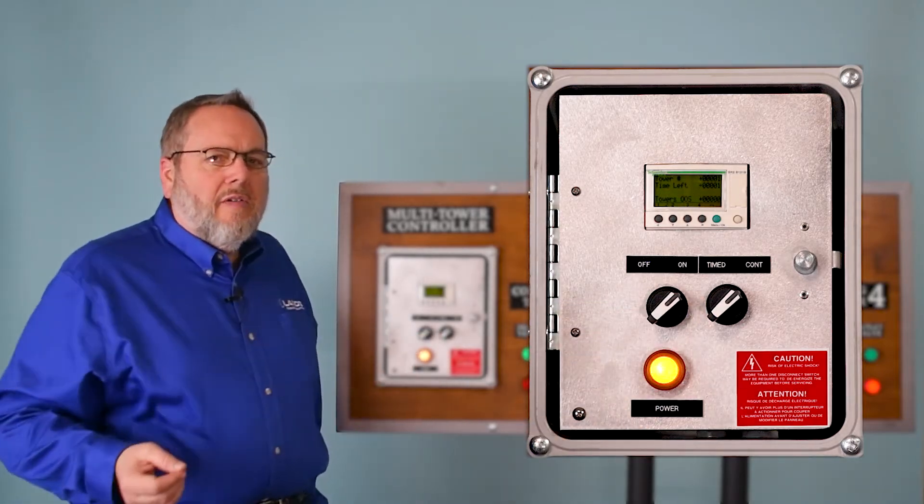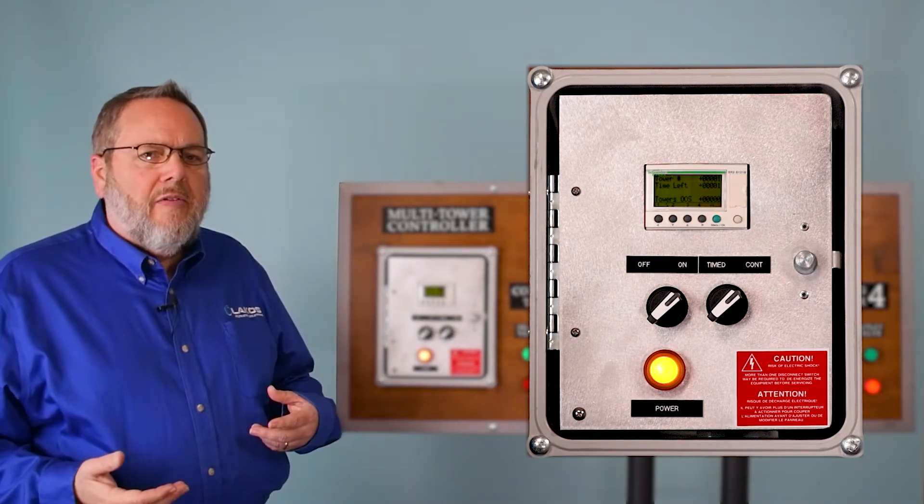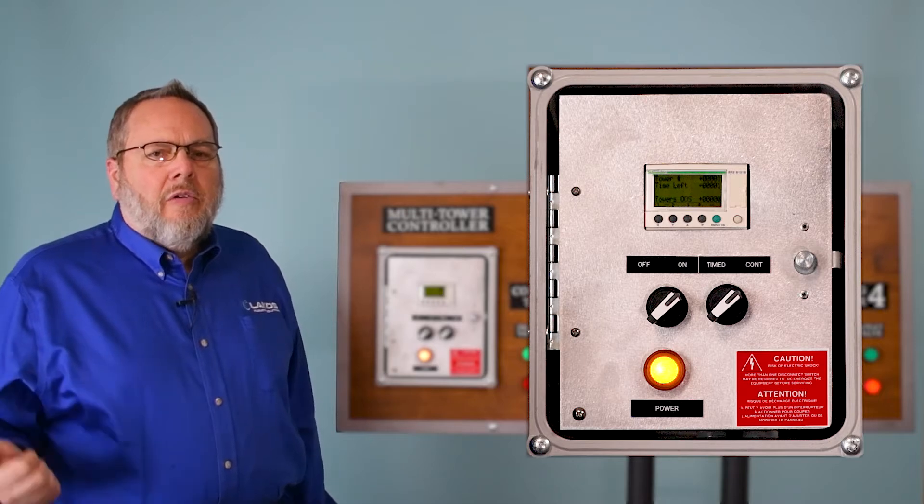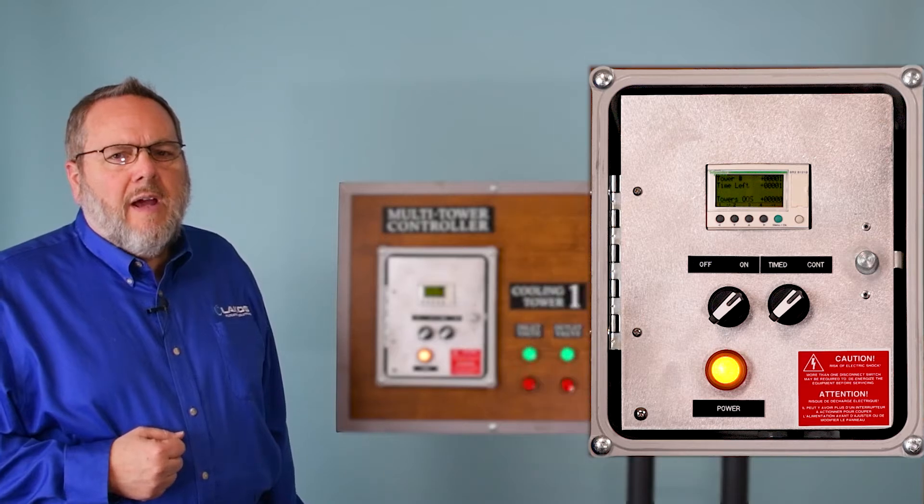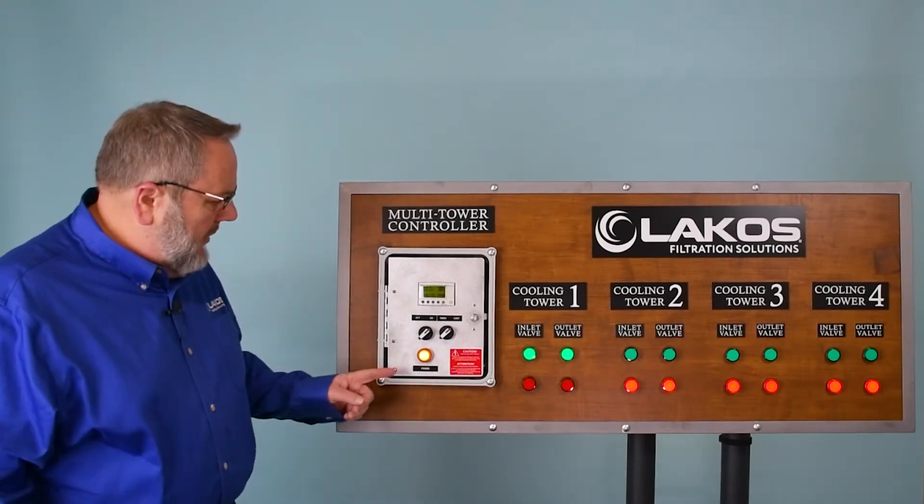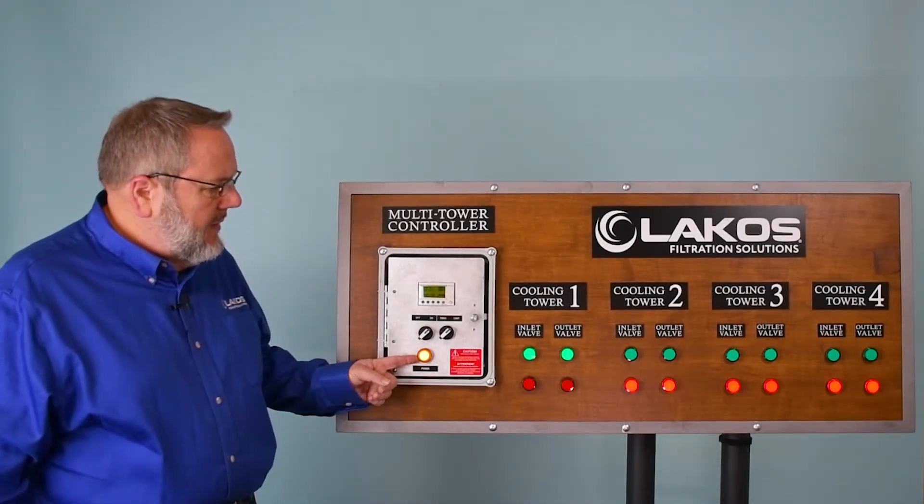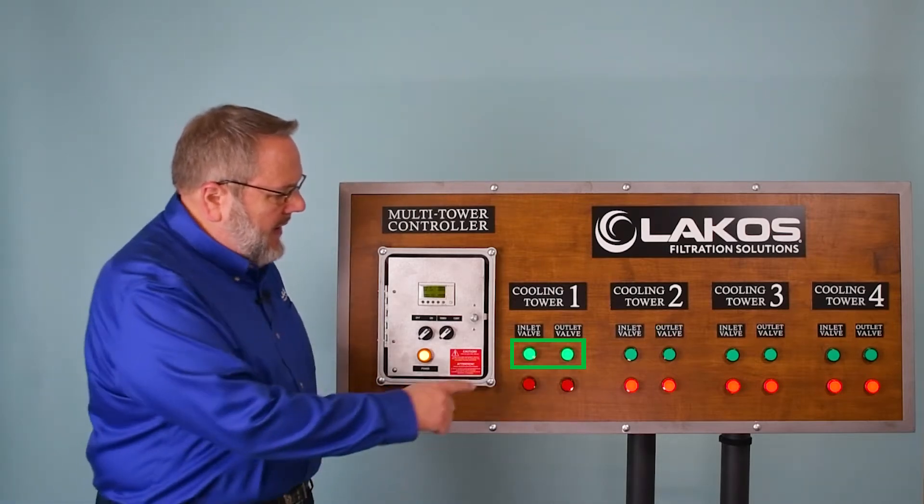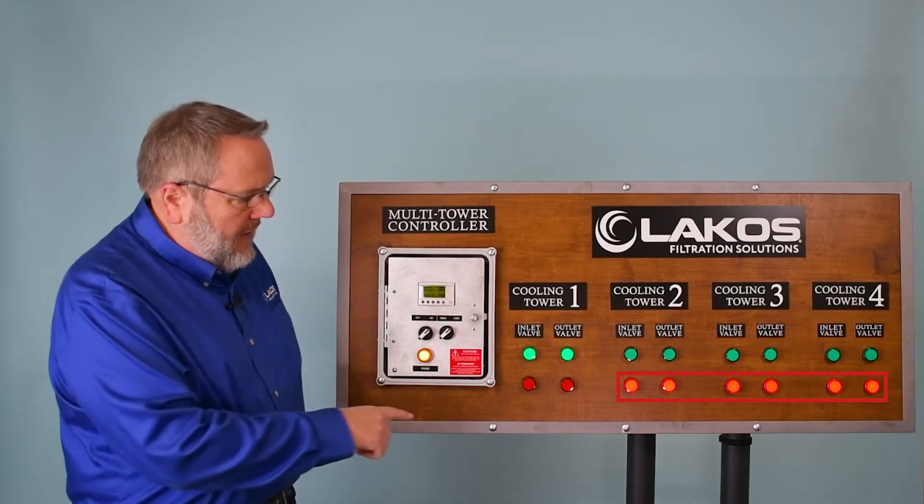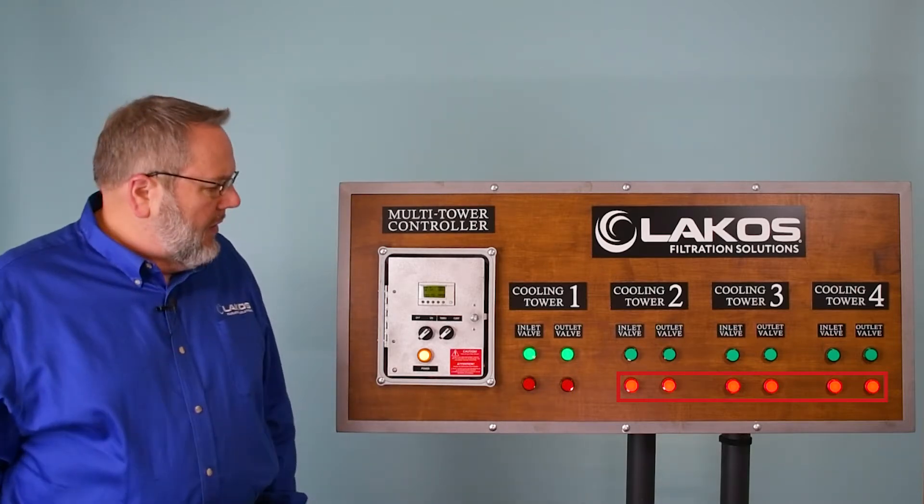If you want to run timed or continuous you will set times based on that. And then also if you want to skip a tower once you get everything set up, we'll show you how to do that as well. Again you can see here the power light is on. You can see here right now we are on tower one. The inlet and the outlet valves are open. The other towers are red which means they're closed.